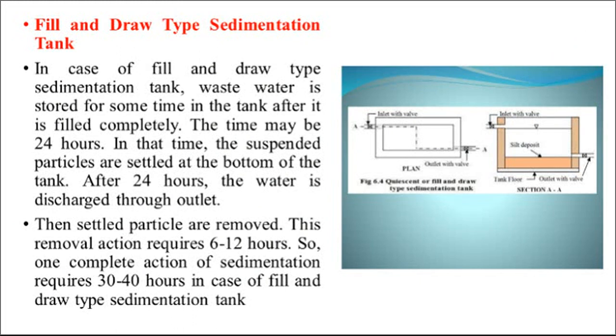In the case of fill and draw type of sedimentation tank, wastewater is stored for some time in the tank after it is completely filled. The detention time may be 24 hours, during which the suspended particles settle at the bottom of the tank. After 24 hours, the water is discharged through the outlet and the settled particles are removed. This removal action requires about 6 to 12 hours.